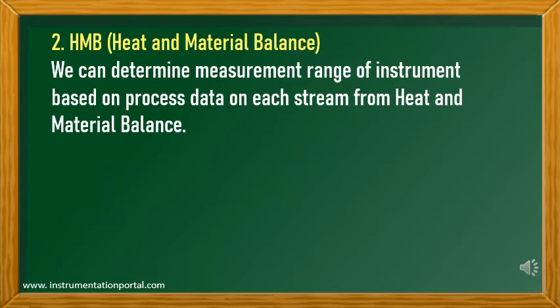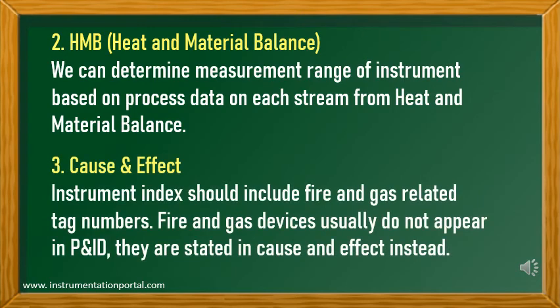Second, HMB or Heat and Material Balance. We can determine the measurement range of instruments based on process data on each stream from the heat and material balance. Third, Cause and Effect. The instrument index should include fire and gas related tag numbers. Fire and gas devices usually do not appear in P&ID; instead, they are stated in the cause and effect.